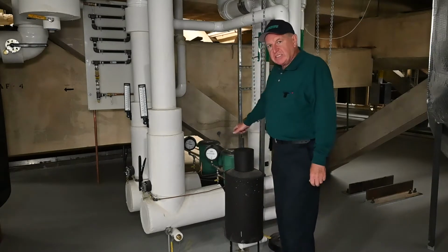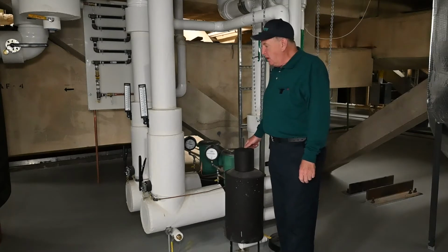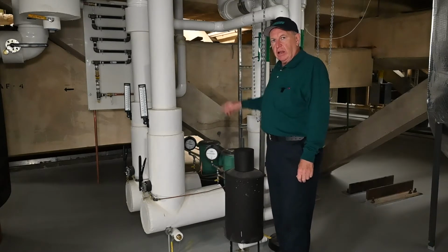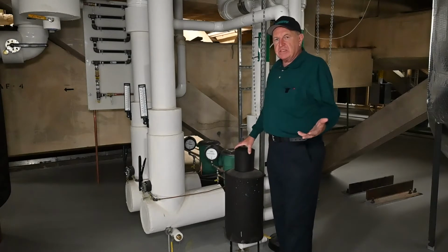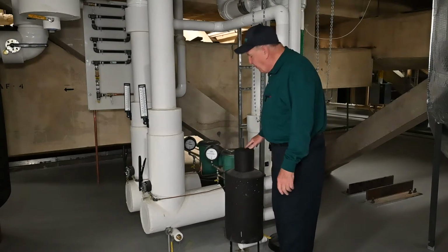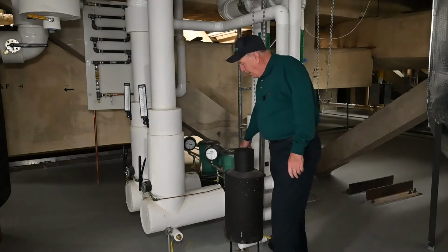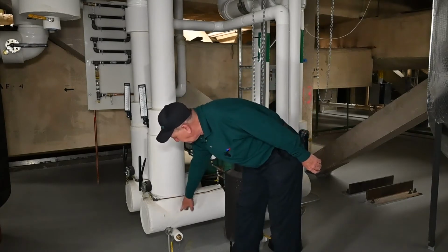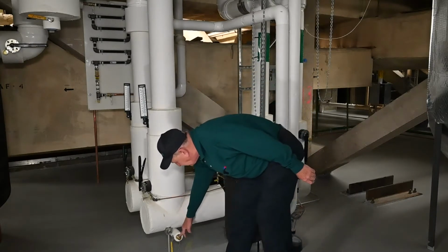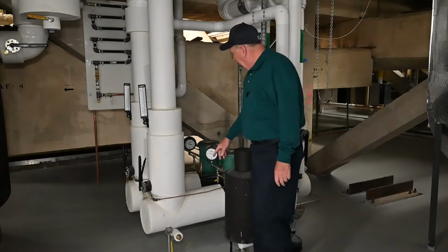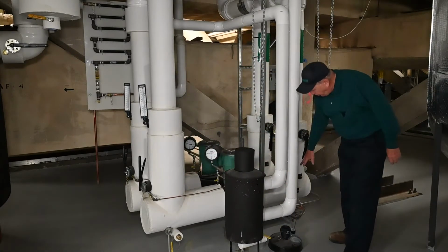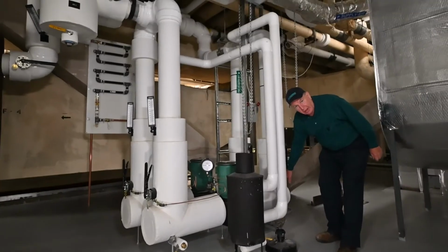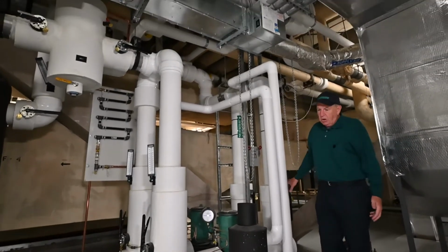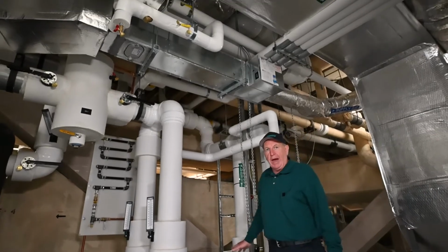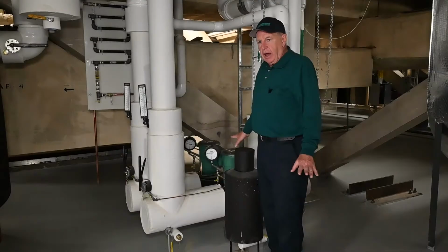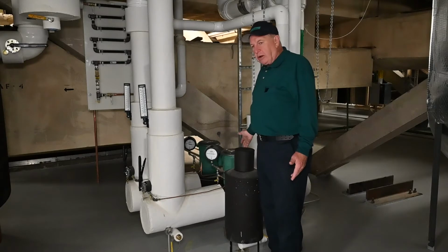There's two 7.5 horse Taco pumps that feed the chiller and the air handler for the Rare Books 4th, 5th, and 6th floors. The 7.5 horse Taco pumps have a suction diffuser. There's a screen in here, and there's a drain on it to flush it. There's also a triple duty valve over here, which is a balancing valve and check valve. The system's all been professionally balanced, so you don't change any settings. The pumps are going to run automatically.